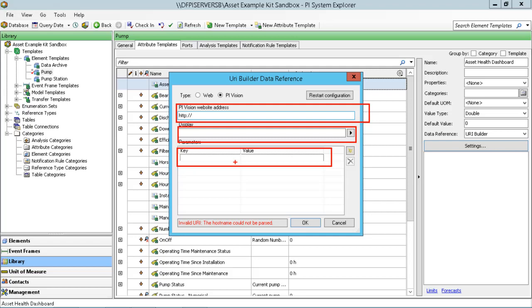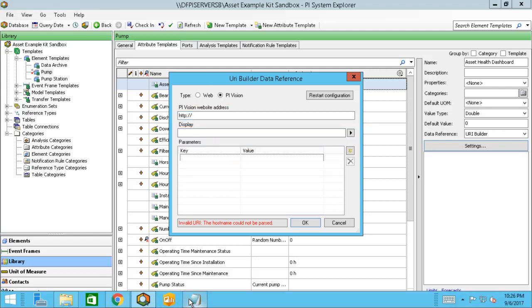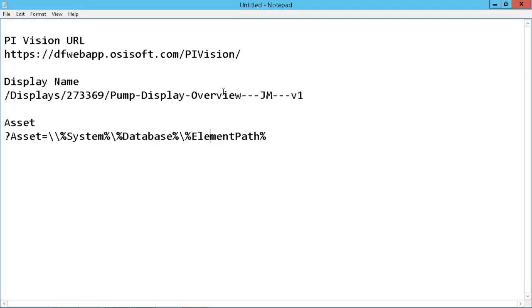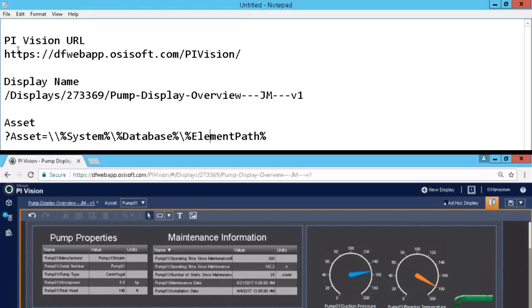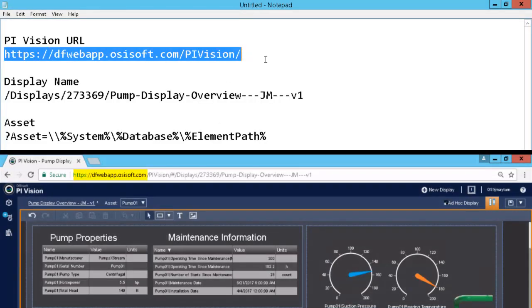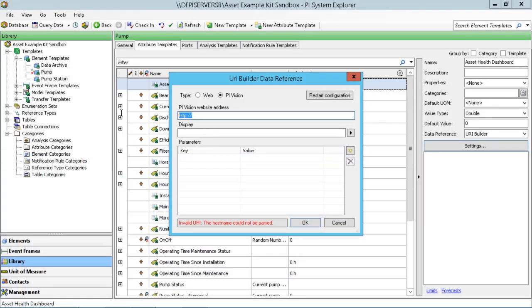You'll recall when we were going through and using the dashboard, we can actually swap between the pumps. What we really want is to open up this display and have it set the asset context to the pump that generated the notification. Our PI Vision URL is right here — that'll be the URL of your PI Vision server. We'll go ahead and copy and paste that into this portion here.